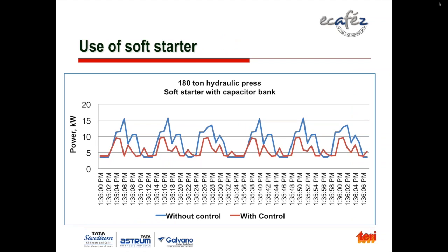Now, the graph in blue is without any control, without any soft starter or capacitor bank. And as you can see, there are peaks in that. So what essentially a soft starter does is that peak load is cut down, and the red line is what is after the installation of soft starter and capacitor bank.